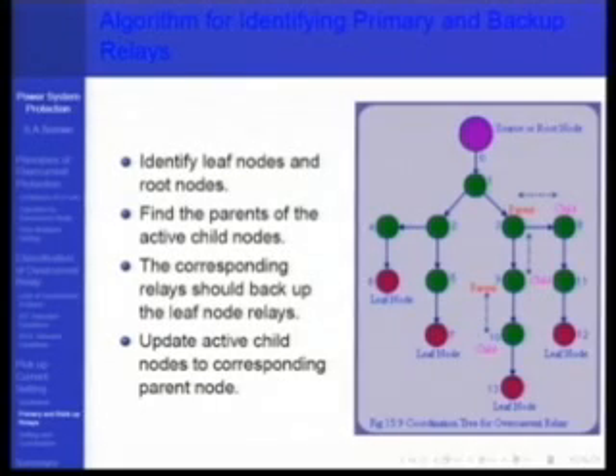Now, supposing that you are going to do overcurrent protection all along, this is how we will do it. This is a single source system. Typically plain overcurrent protection will be used for single source radial systems, not even multiple source radial systems. And you start with the leaf nodes here, because these have no coordination constraints. So there is a feeder here in principle. I am just showing the relay location here. This relay does not require any coordination with any other relay, so it should be set first.